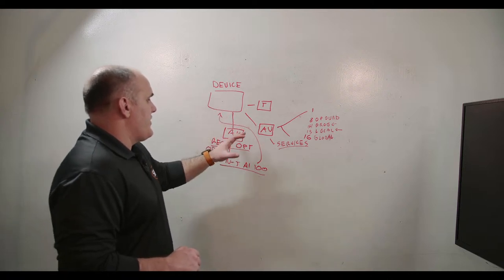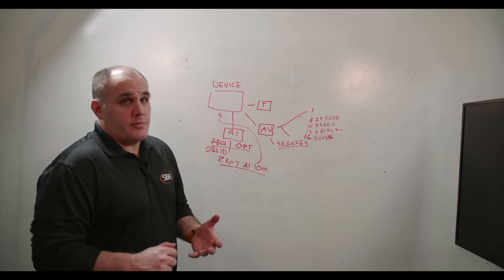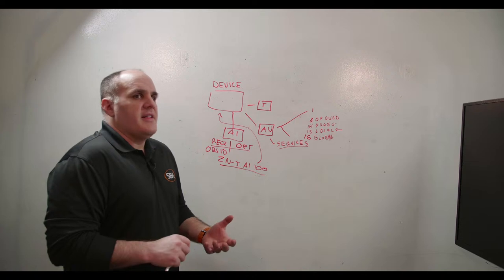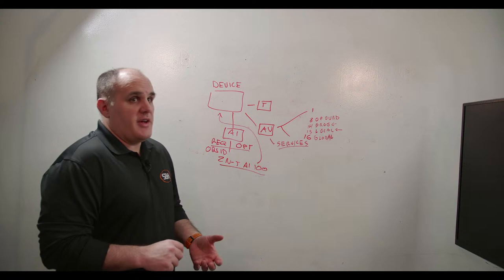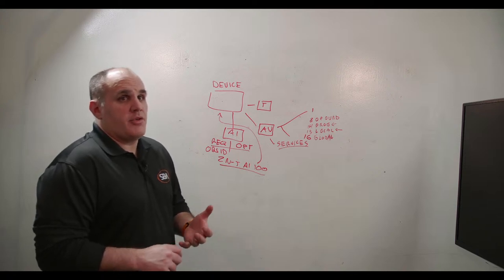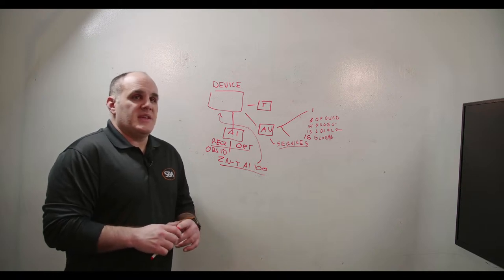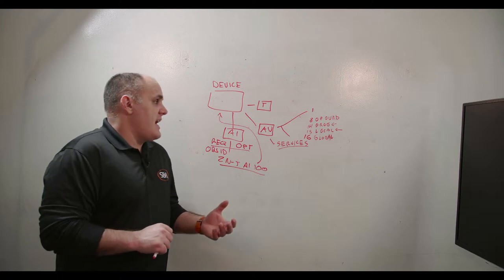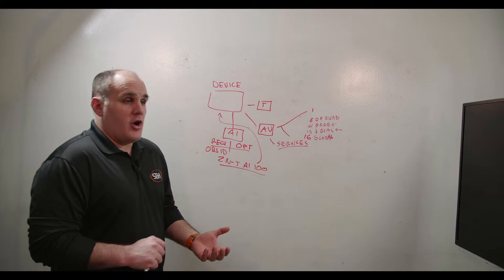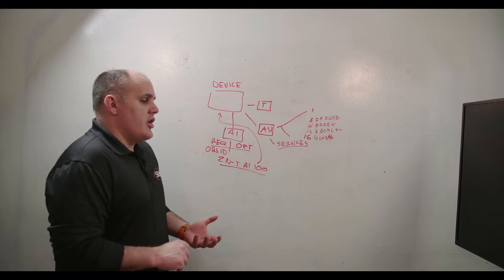To recap: we've got a device, objects nested under the device (like AIs and AVs), objects have properties, and they support services. Now there's BACnet Testing Laboratories — BTL. BTL confirms that BACnet devices match a BACnet profile. You have profiles like advanced application controller, application specific, building controller, etc. Those profiles support different BIBs — BACnet Interoperability Building Blocks — which are sets of functionality. Reading a BTL listing and evaluating the BIBs tells you what that device should and should not be able to do.